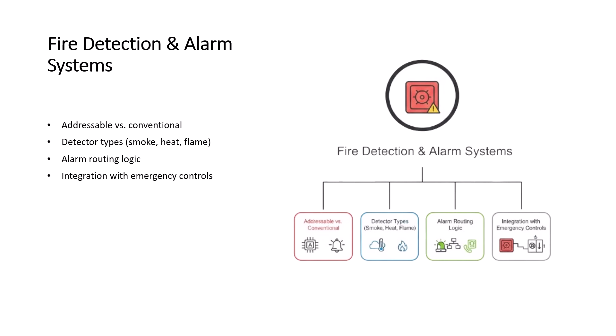Now we'll talk a little about the integration of fire systems with our BMS. First, the benefit of integration of fire with BMS is automatic HVAC shutdown. Once there is a fire event, our HVAC system will be switched off automatically by the BMS. This is done mainly to prevent the spreading of fire via ducts, because air is continuously flowing through our ducts and AHUs. Then is the elevator recall, where elevators must be recalled and monitored by BMS if there are issues with the fire system, so elevators are immediately turned off for maximum protection of occupants, so that when people are rushing to evacuate, the elevator is not an obstruction for them.